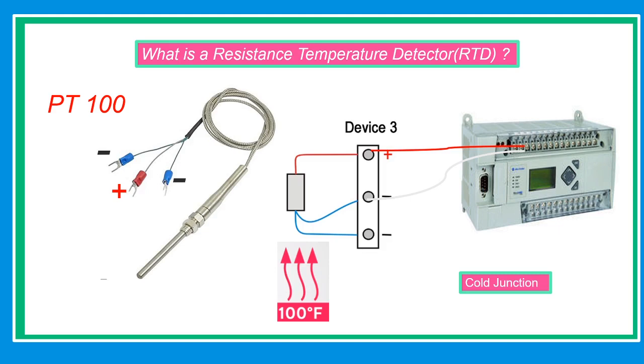RTD, or resistance temperature detector, is a temperature sensor that works on the principle that material's electrical resistance changes with the changes in temperature. PT100 and 1000 are the most common RTD sensors on this type of resistance temperature application. The most common metal used for precision resistance measurements is platinum because it is good and stable metal, corrosion resistant, and does not oxidize readily, and is easily workable into thin wire.